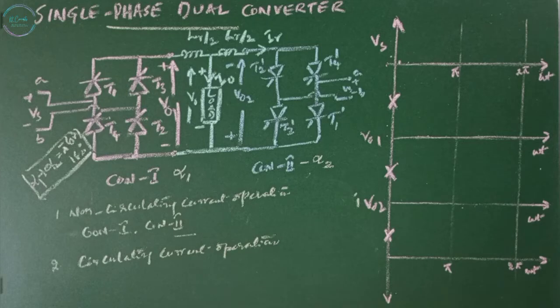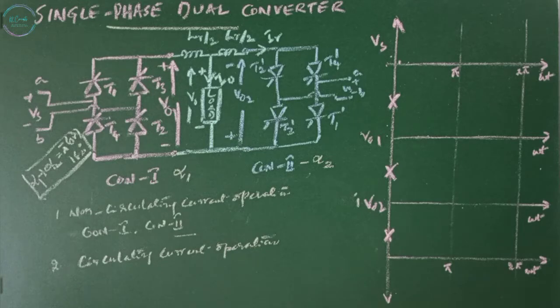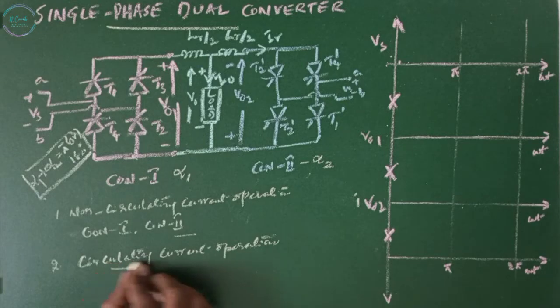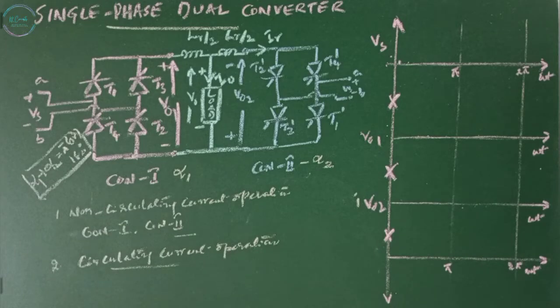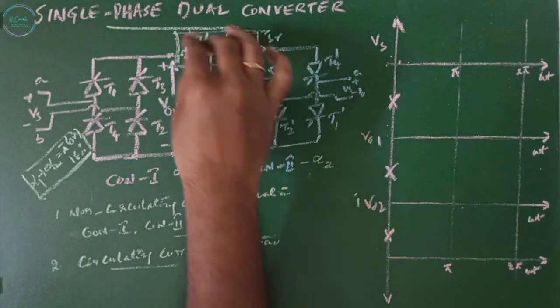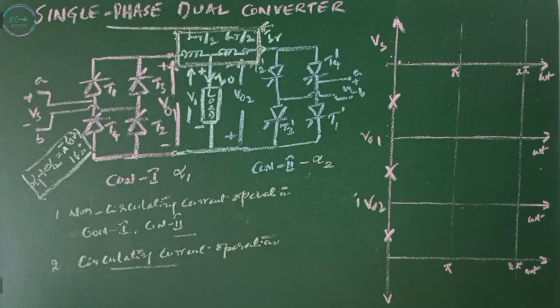In circulating current operation mode, both converter one and converter two operate at the same instant, where converter one operates as a rectifier and converter two operates as an inverter. This creates a problem of circulating current. This circulating current does not flow through the load but circulates between the converters. It can be managed by a reactor circuit that limits the circulating current within acceptable limits.